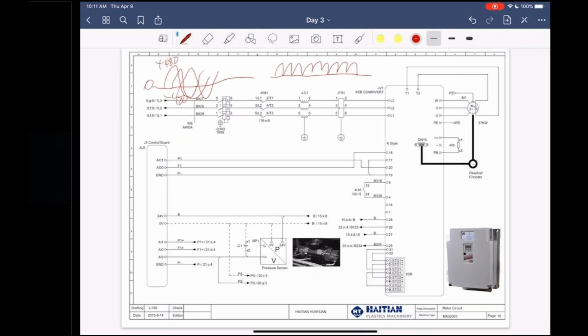Then it goes to a rectifying system, which converts it to a DC signal, which makes it a straight line. The DC voltage is the incoming voltage times 1.414, which is the square root of 2. So if you would check the power coming out of the plus plus minus minus, which is your DC bus, you would have 480 volts times 1.414, and that would be a DC voltage.